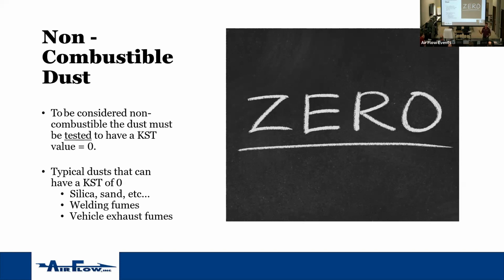They will actually take the dust, they grind it up, they throw it into a pressure chamber, they throw it across the hot wire that ignites it, and you will actually get a rating. And if it doesn't explode, you'll get a KST of 0. If it does, you could have a KST of 2. If your KST is that small, it's explosive. You have to follow ST1 class safeties.